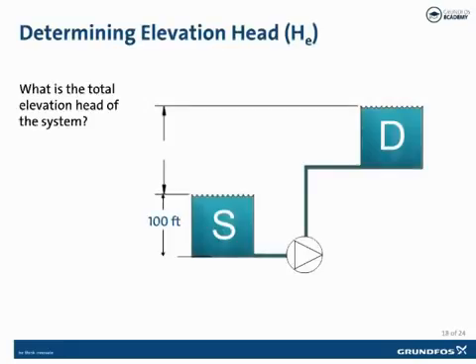To calculate the elevation head in the system, it is the height differential between the current elevation of the fluid and the final elevation the fluid is to be pumped, calculated from surface to surface. In the example shown here, from the surface of the suction tank to the upper surface of the discharge tank, the difference is 200 feet. Therefore, the elevation head in this system is 200 feet.